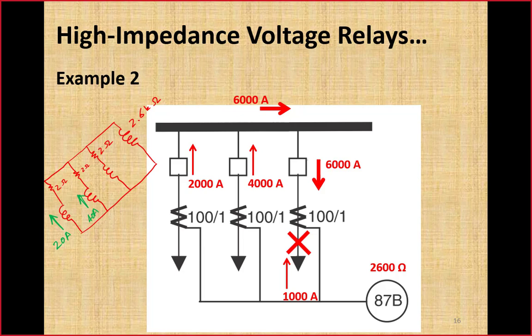Here the direction has been reversed in this circuit, and that is 60 ampere. Now due to the complete saturation of this CT, due to carrying such a high current, this magnetization branch will get short circuited due to the saturation of the CT. Now this 20 plus 40 ampere current will take this path through this series impedance and will result in a voltage drop in this polarity, and then through the short circuit and back to the branches.